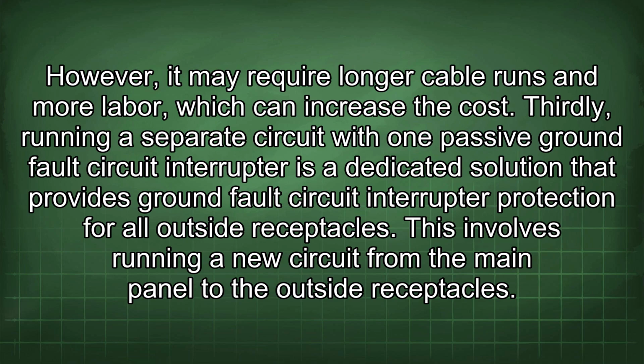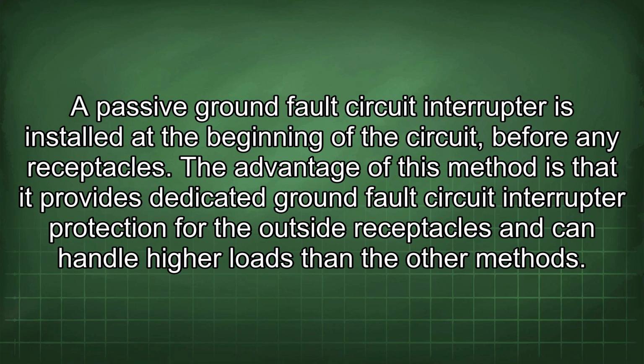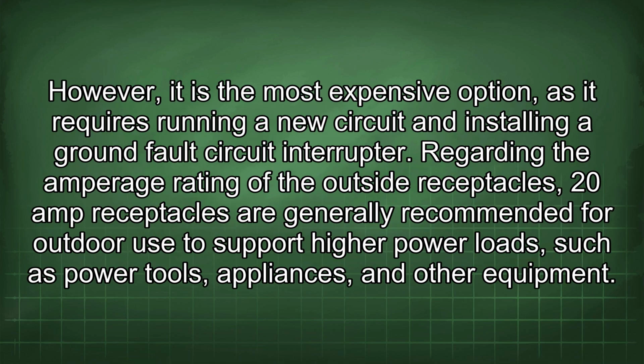Thirdly, running a separate circuit with one passive ground fault circuit interrupter is a dedicated solution that provides ground fault circuit interrupter protection for all outside receptacles. This involves running a new circuit from the main panel to the outside receptacles. A passive ground fault circuit interrupter is installed at the beginning of the circuit, before any receptacles. The advantage of this method is that it provides dedicated ground fault circuit interrupter protection for the outside receptacles and can handle higher loads than the other methods.